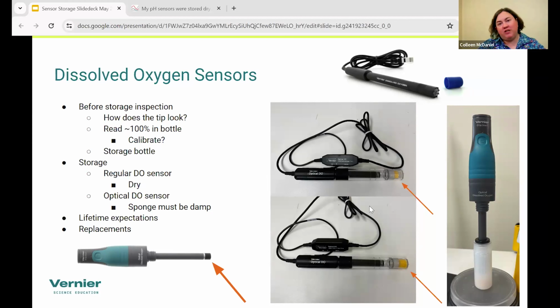If the sponge and the optical DO probe does dry out, it's not the end of the world, which is really nice about this probe: a dry sponge isn't going to destroy it. Basically, what I tell people to do is just make sure to get the sponge wet again. And if you have to use the sensor right away, I would just soak it in some tap water to rehydrate that membrane and get it ready to start reading.